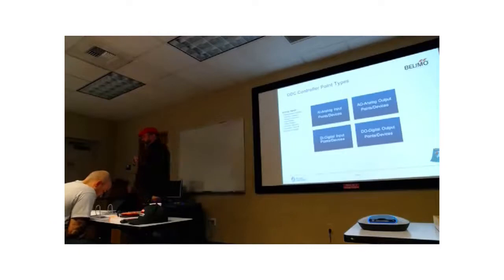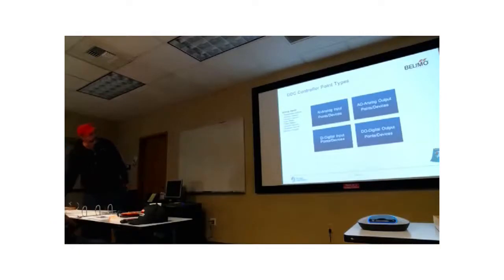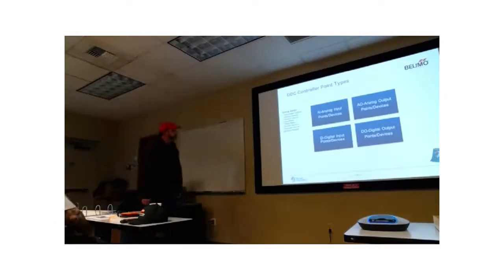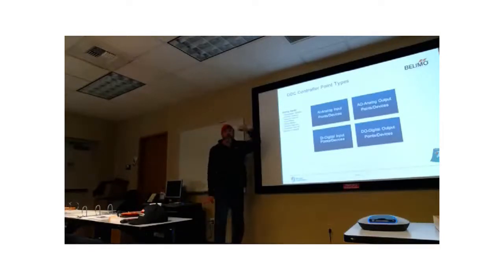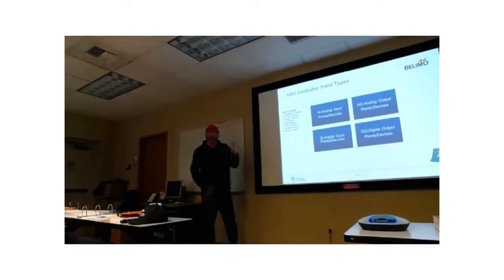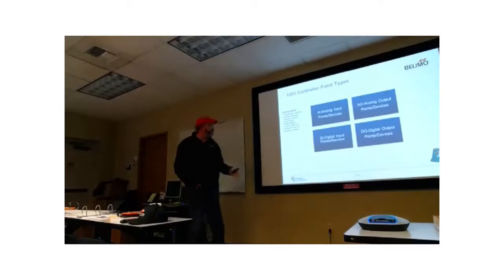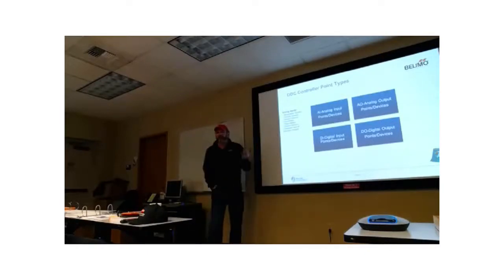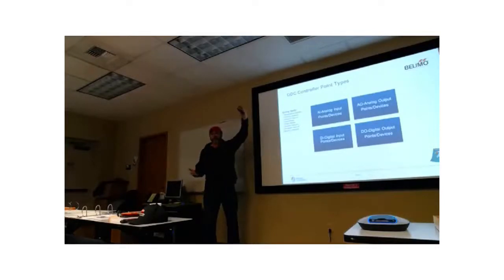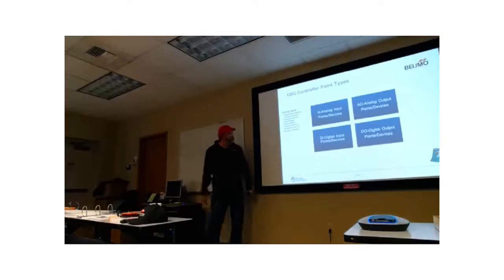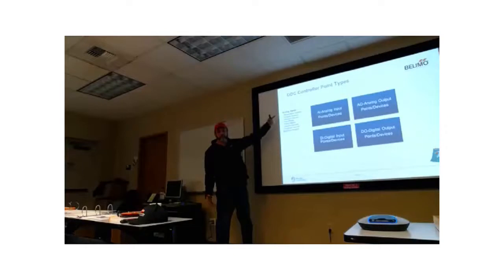You actually have a list of them in your workbook on page 7. You have anything that has a varying signal, right? So a temperature sensor, a humidity sensor, a flow sensor, a power meter, something like that. It's an analog signal. It varies across a given range: 2 to 10 volts, 4 to 20 milliamps, 0 to 5 volts, something like that. So the signal goes across that range, and it has a value of that voltage for every single temperature or position it can take. That's an analog input.